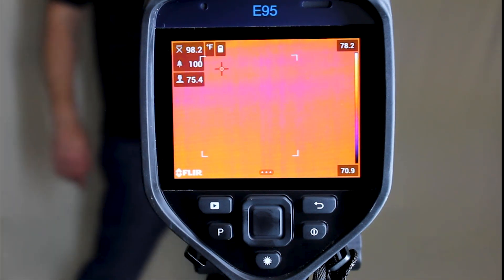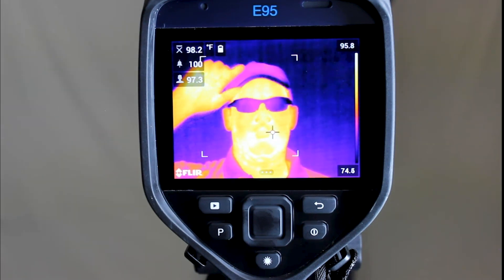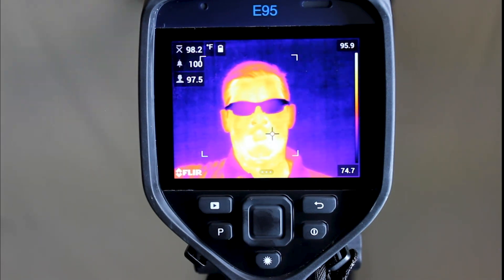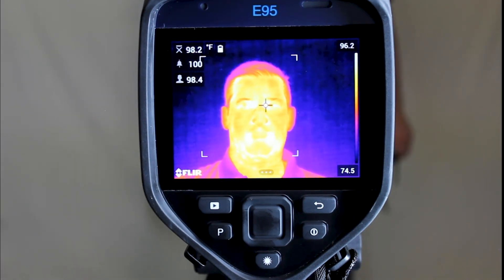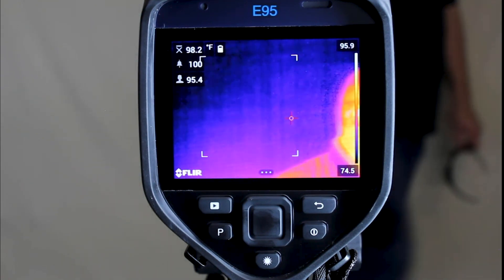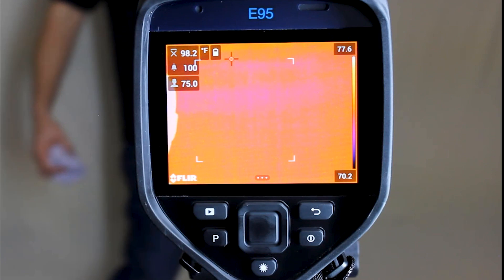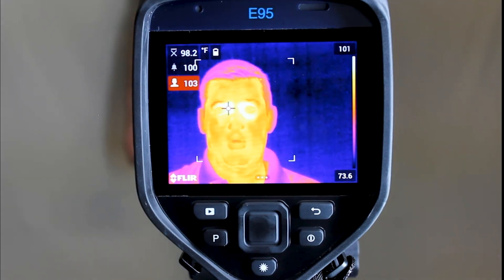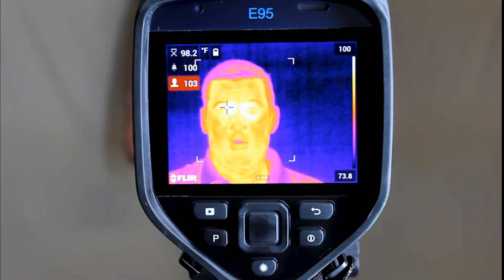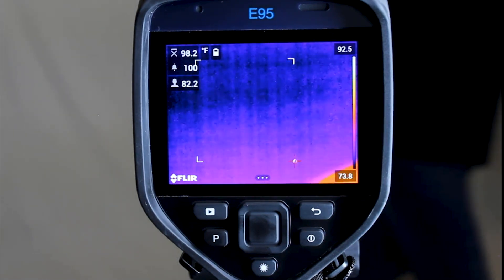During the screening process, you will want to make sure that all hats and glasses are removed prior to screening, as these can impact your readings and provide false information. If you detect elevated skin temperature in a person being screened, please request that the individual be screened using a device designed specifically for measuring body temperature, such as a thermometer.